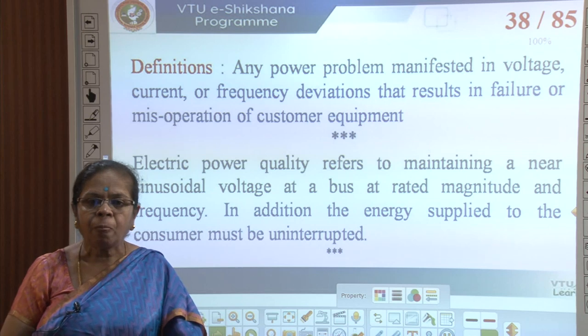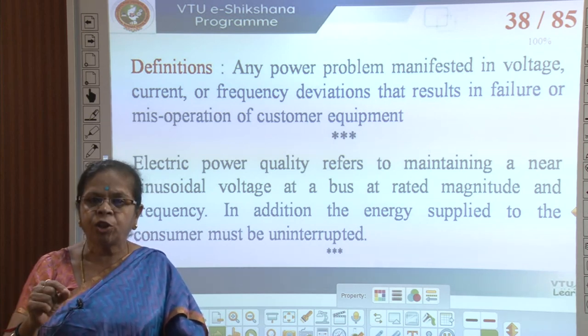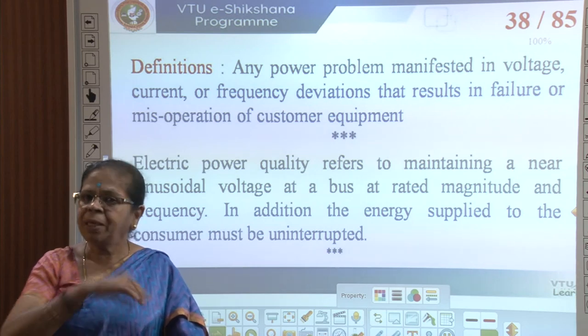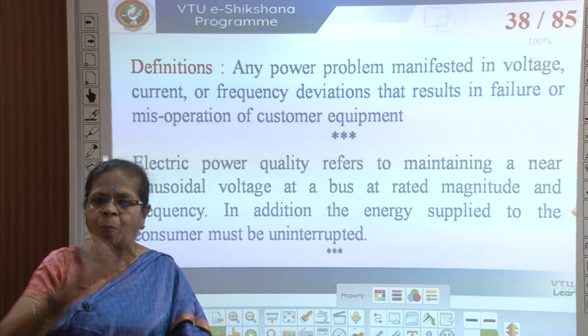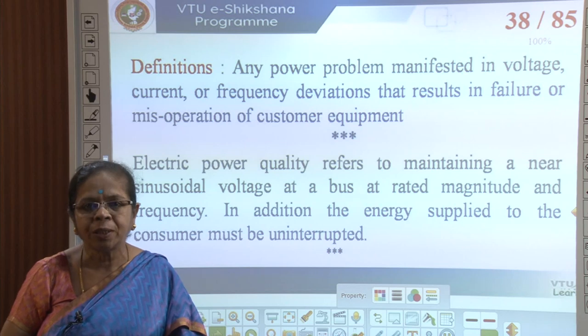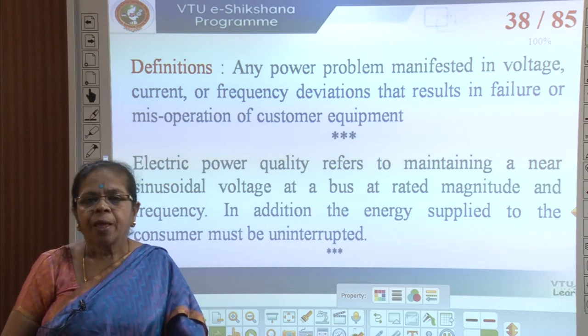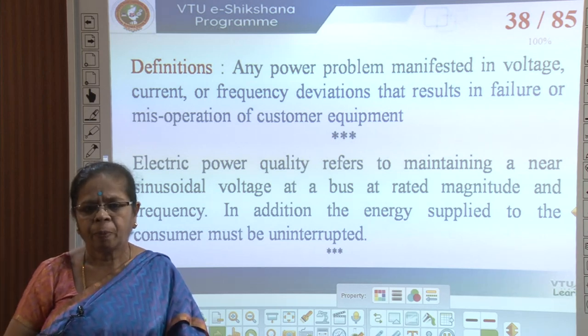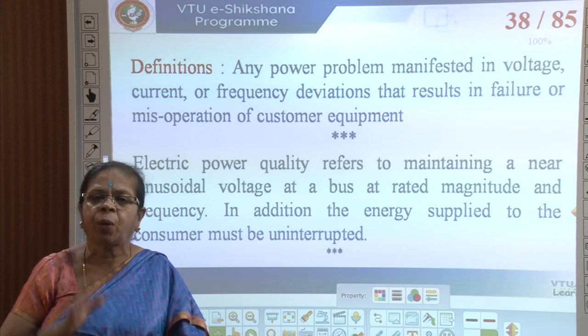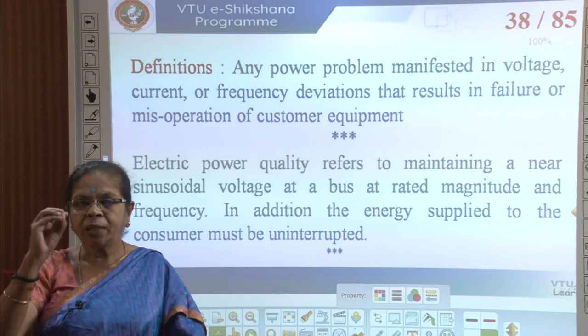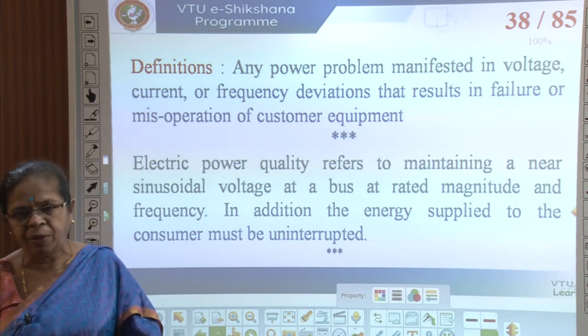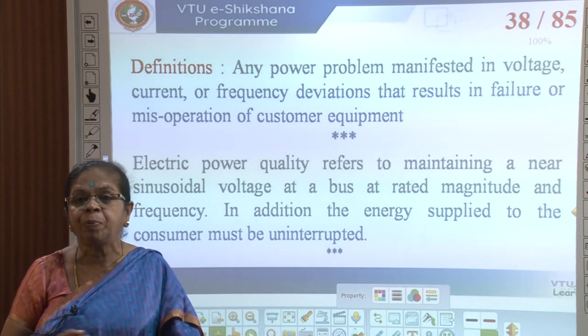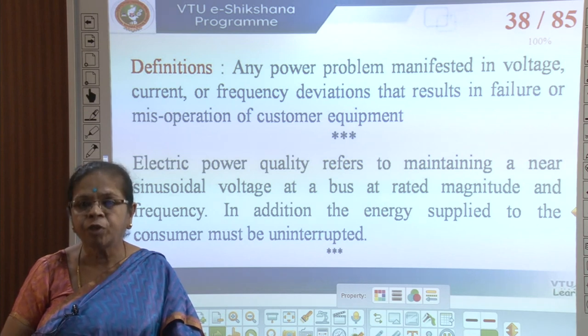Failure means the equipment fails to operate; mal-operation means it does not operate the way it is supposed to. Another definition: electrical power quality refers to maintaining a near-sinusoidal voltage at rated magnitude and frequency at every bus — 132 kV bus at 132 kV, 11 kV bus at 11 kV, 230 V at 50 Hz — and in addition the energy supply to the customer must be uninterrupted and reliable.